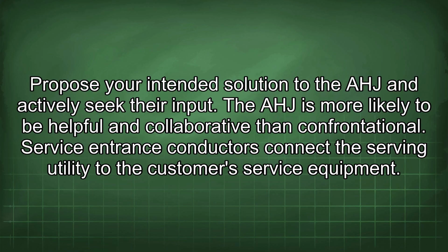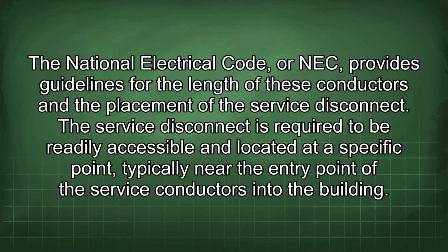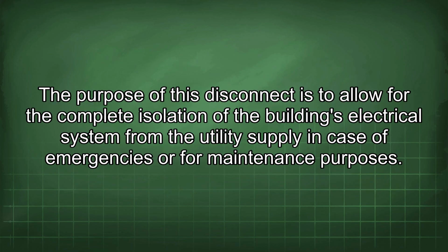Service entrance conductors connect the serving utility to the customer's service equipment. The National Electrical Code, or NEC, provides guidelines for the length of these conductors and the placement of the service disconnect. The service disconnect is required to be readily accessible and located at a specific point, typically near the entry point of the service conductors into the building. The purpose of this disconnect is to allow for the complete isolation of the building's electrical system from the utility supply in case of emergencies or for maintenance purposes.